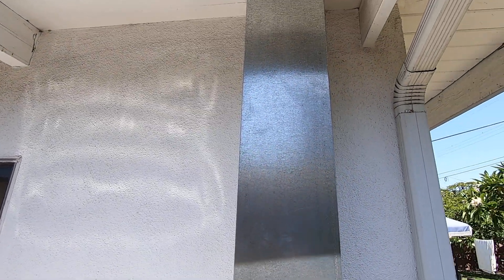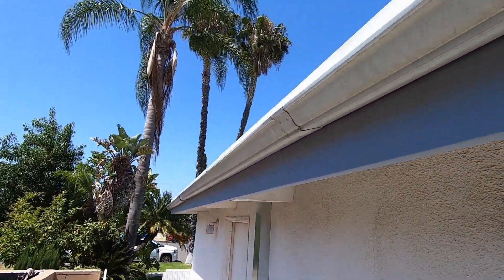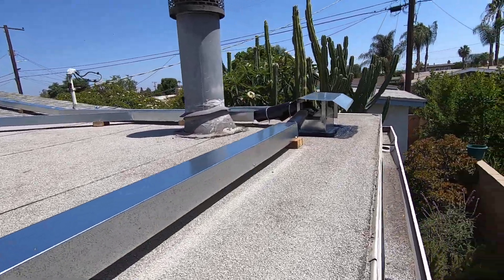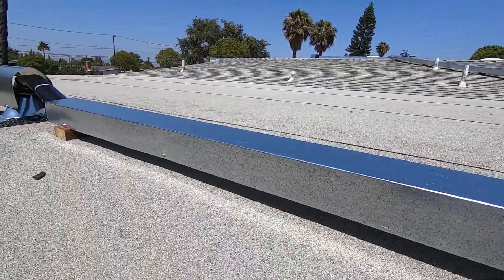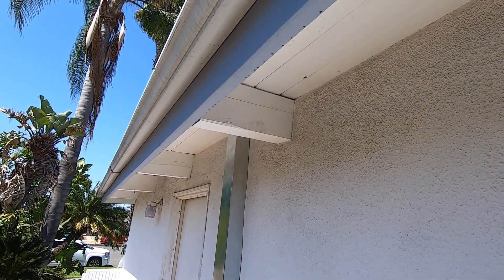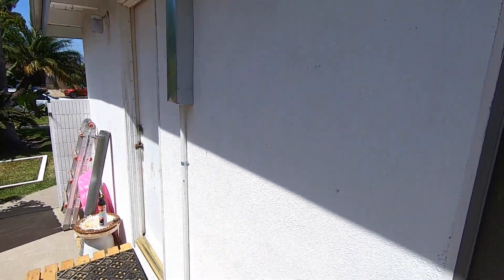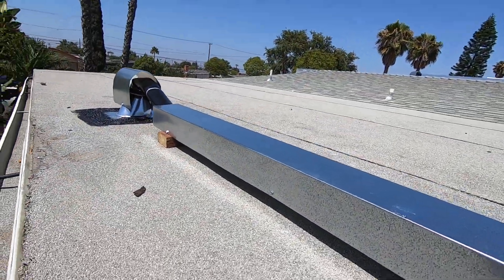We had to go on the roof because this is a high-ceiling house with no attic. As you can see, the lines come up on the roof and then run in line covers all the way over, down underneath the eave with flashing, and down in that line cover where it attaches to the back of the condenser.